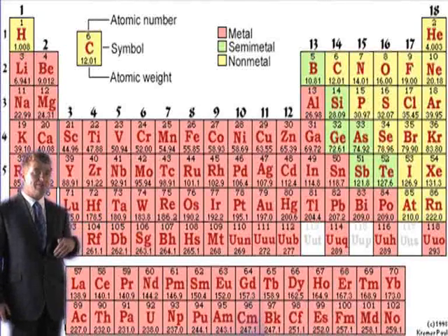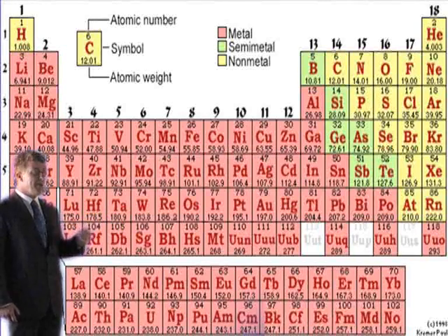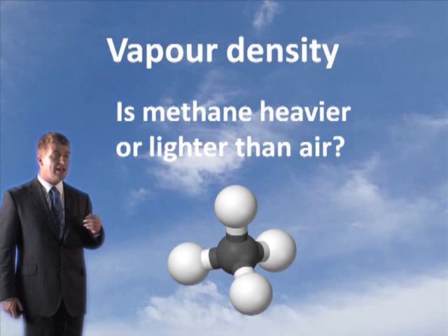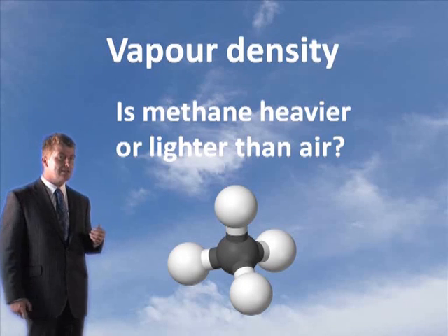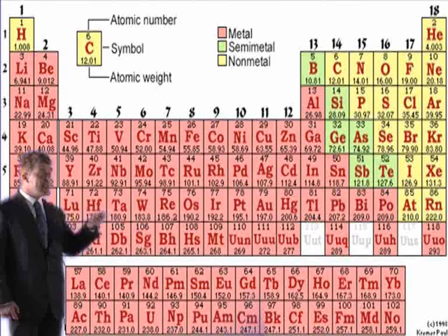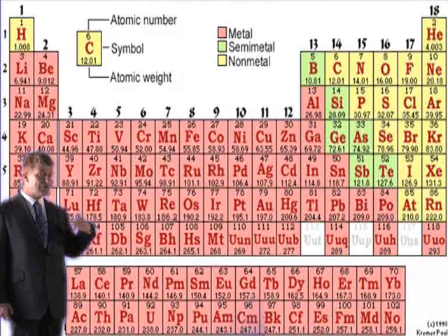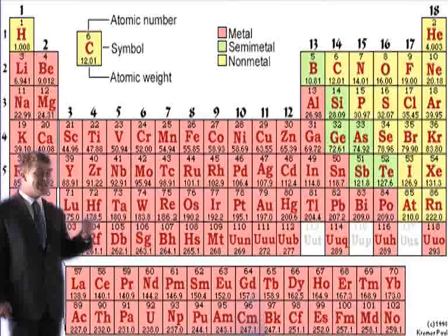So CO2 is heavier. What about methane? Is methane heavier or lighter? Think of methane gas, like a sewer gas. Let's have a look. CH4, carbon is 12, hydrogen is 1, so methane is 16. It is lighter than air. So where's that going to collect? Up high. So you need high level ventilation.